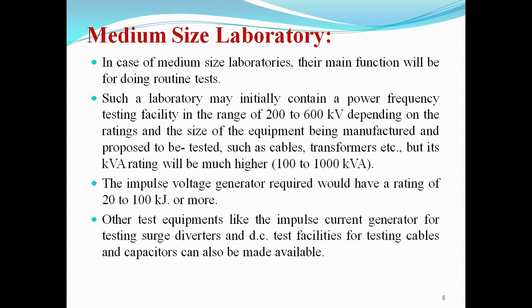Other test equipment like the impulse current generator for testing surge diverters, and a DC test facility for testing cables and capacitors can also be made available. So it means sometimes not only the high voltage AC transformer, impulse generator, and DC test unit, but also the impulse current generator is there in the high voltage laboratory.